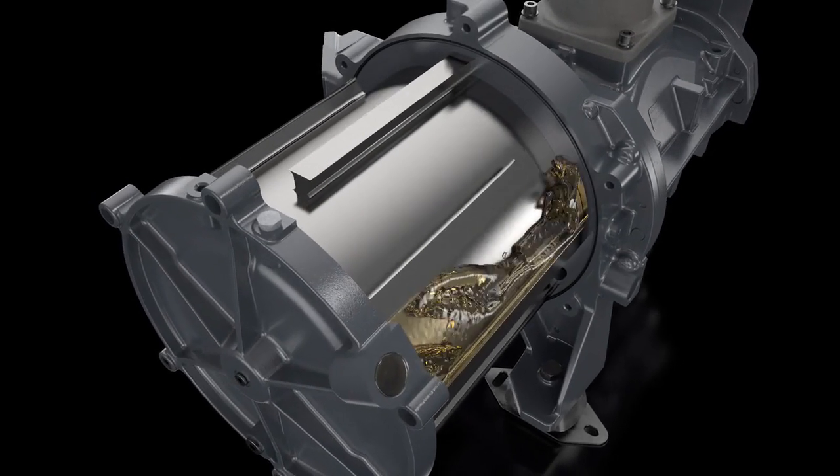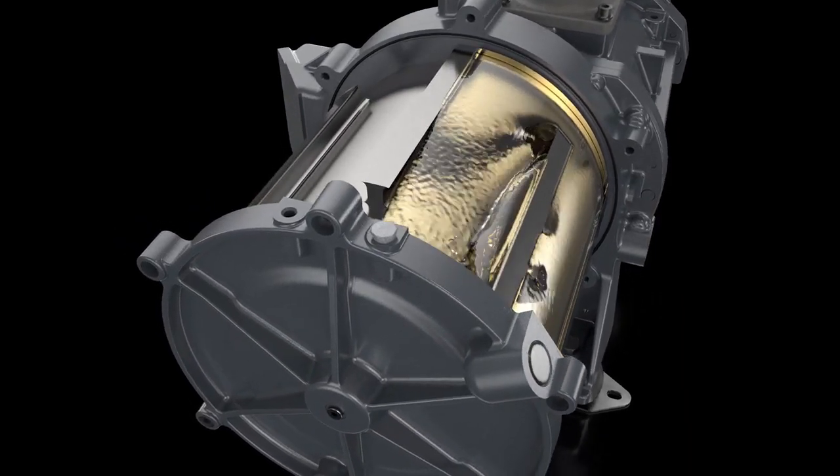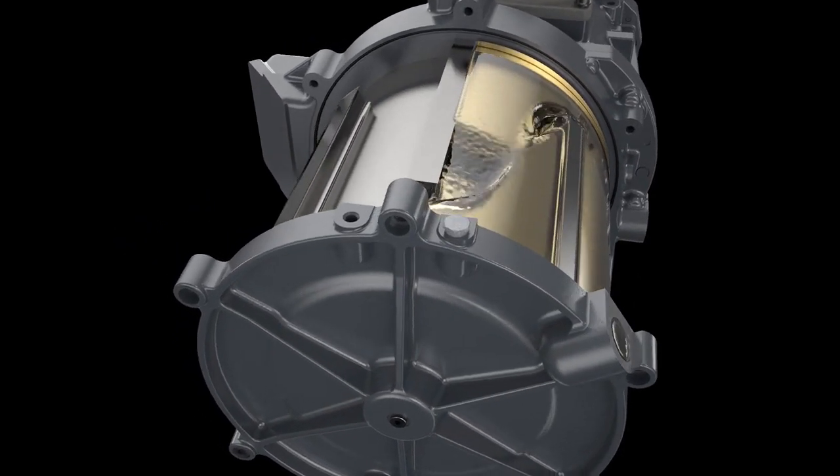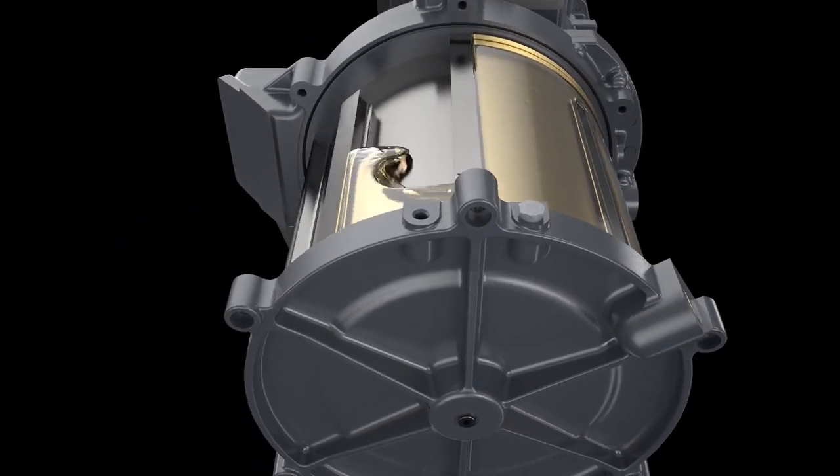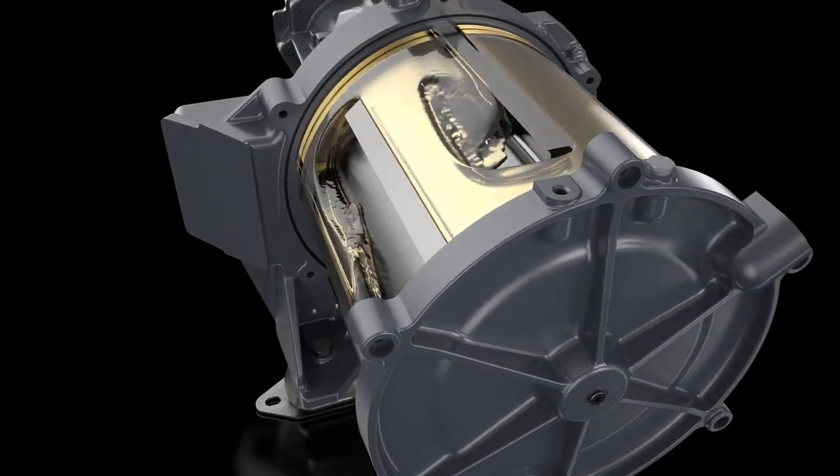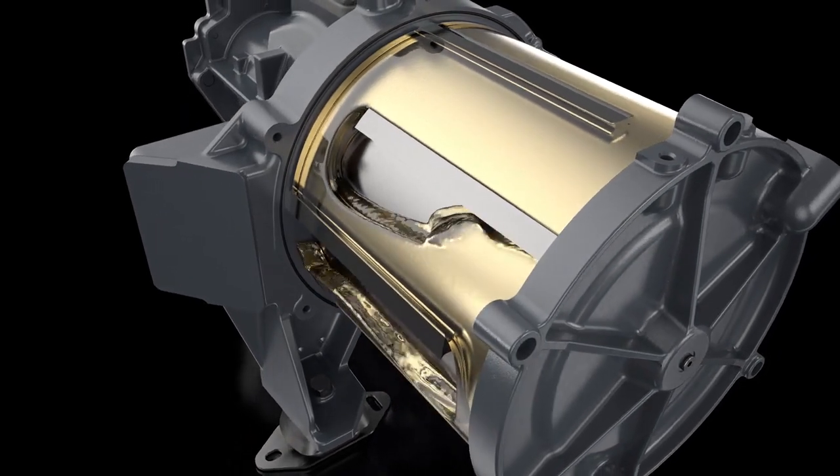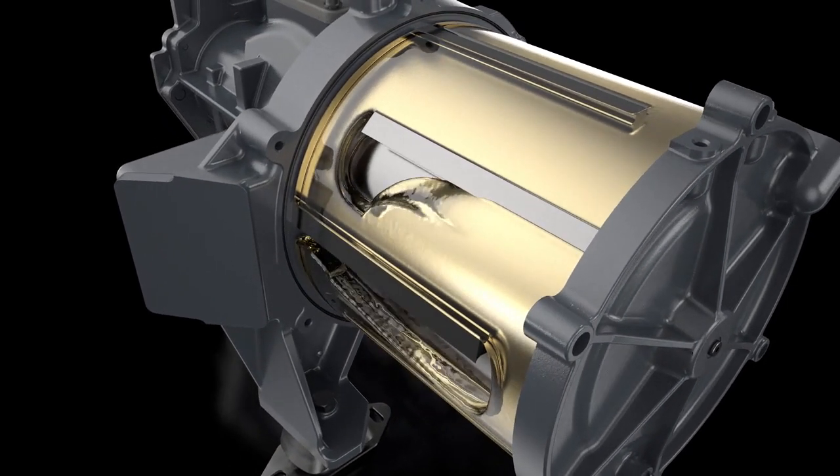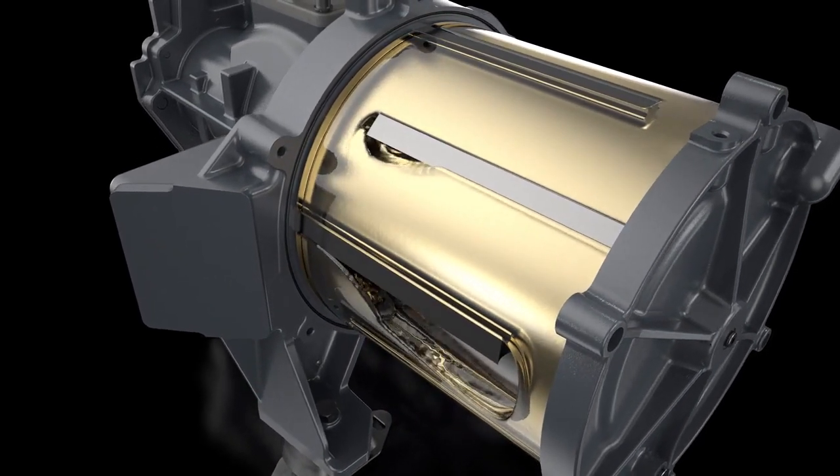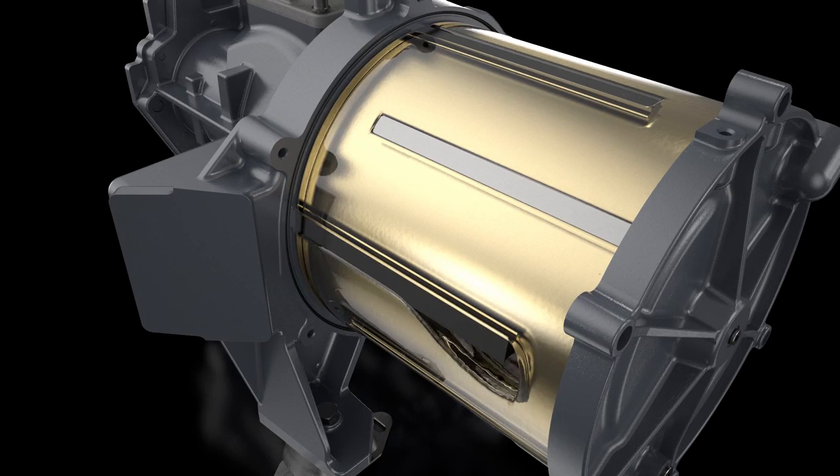Oil is injected in the motor housing and runs through canals around the motor, cooling it evenly. The oil then continues to the screw element, where it lubricates and cools the rotors. This process is repeated over and over. If the oil gets too hot, it runs through the oil cooler first, before returning back to the motor.